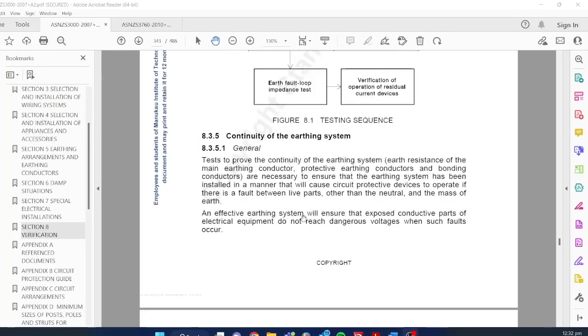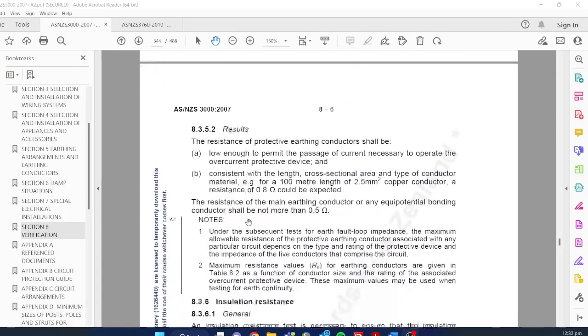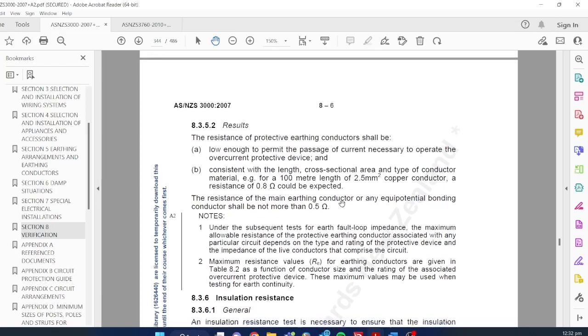So let's scroll down then to here, where it tells us about the continuity of the earthing system. I'm not going to read that in detail for you. You can find that yourself, 8.3.5 of AS/NZS 3000. And if we look here, results. So what does the value need to be when I do that test? Well, it says here that resistance of the main earthing conductor or any bonding conductor should not be more than 0.5 ohms. So our main earth and our bonding conductors must be 0.5 or less. And if I look down here in the notes, it says maximum resistance values for earthing conductors, so that's out to our sub-circuits, are given in table 8.2 as a function of conductor size and rating of the associated overcurrent protection device.